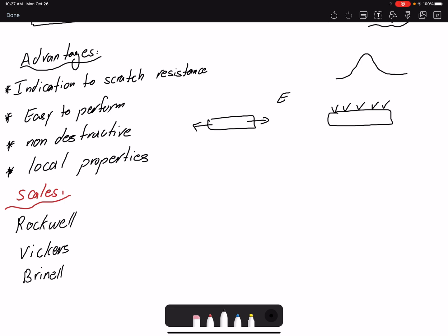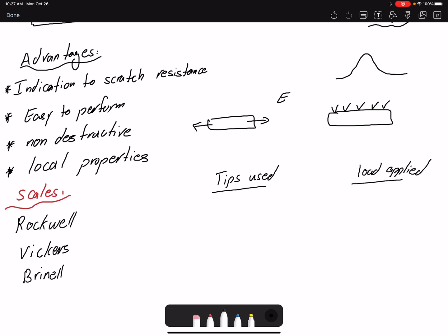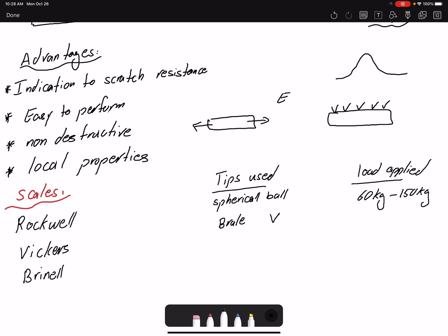The difference between these scales is the tip being used and the load applied to the specimen. The common tips are a spherical ball or a Brale, which is a three-sided tip. The range of load applied spans from 60 kilograms to 150 kilograms depending on the scale used.